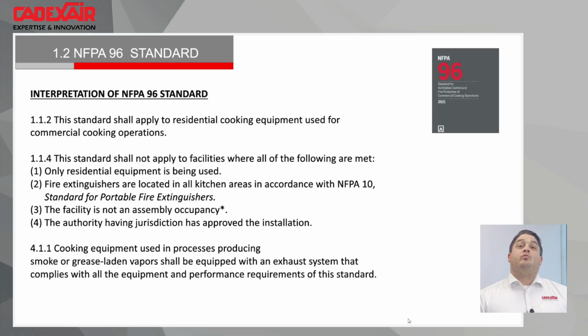Article 1.1.4 is very important. It's when the standard will not apply as per NFPA 96. First, you need to only have residential equipment to be used. Second, you need to have the right portable extinguisher around the system. So if you have a residential hood with everything, you still need to have an ABC kitchen extinguisher. And normally when we are in a commercial cooking exhaust system, we will use what we call a type K extinguisher. It's a specific extinguisher built for grease fires, but this extinguisher will conduct electricity, and that's why when you get a fire in a commercial exhaust hood system, we need to shut down the appliance to reduce the risk of electrocution if somebody uses a portable extinguisher on the fire.